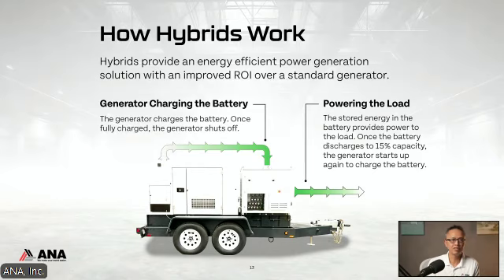When you lightly load a generator, it becomes very inefficient. But when you're heavily loading it, it becomes very efficient. What you want to do is run that generator when it's nice and efficient, and store that energy into the batteries. Then, if you can, turn off the generator and run that load off of the batteries. There could be some incidences where you have a higher load, and if that's the case, you want to run that generator continuously, because it's already at its optimal efficient condition at that higher load.